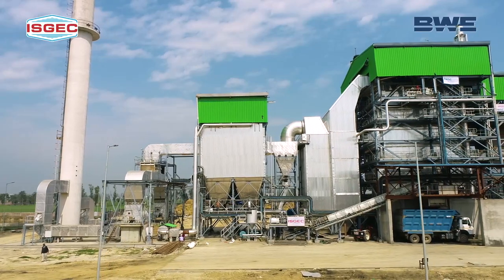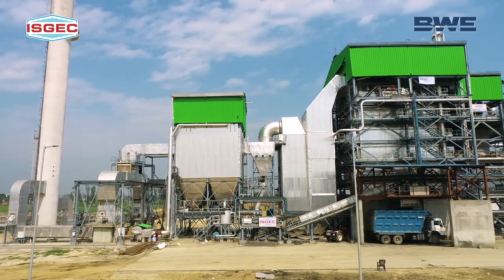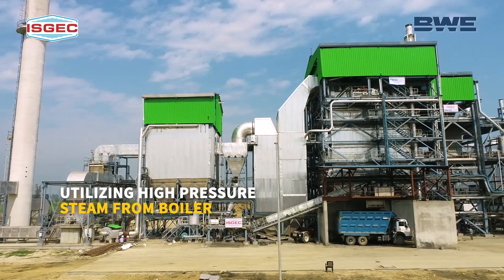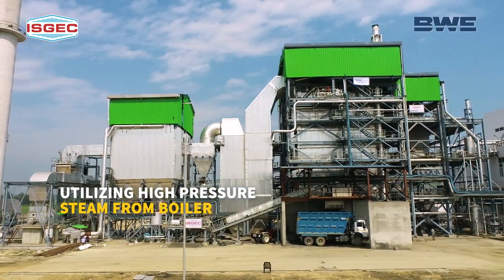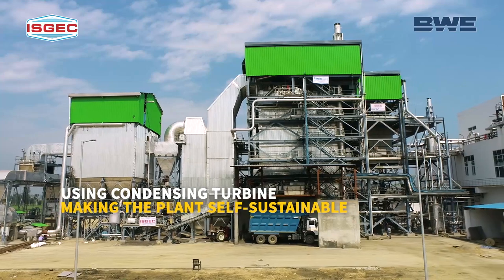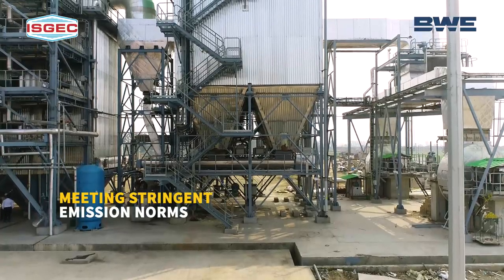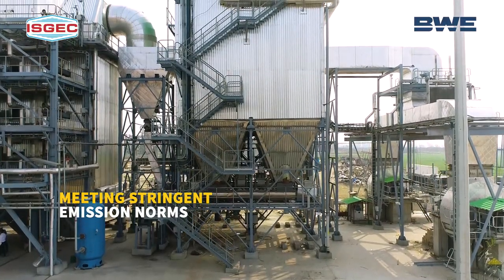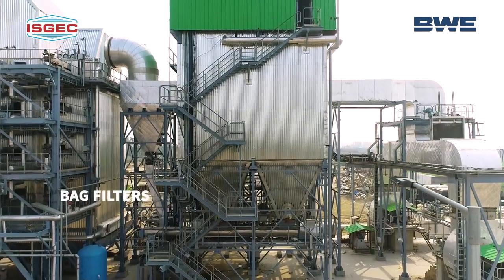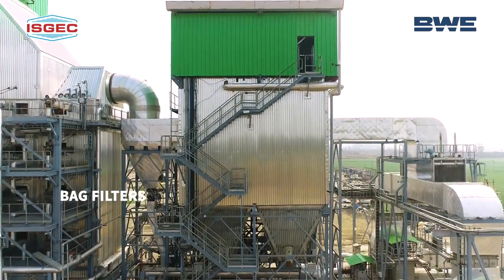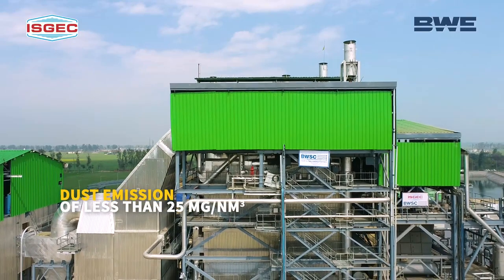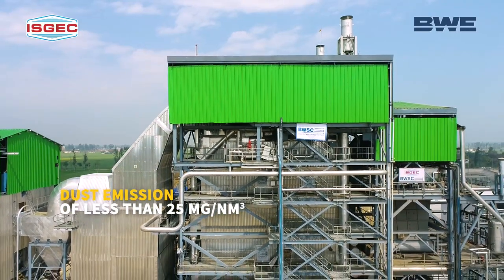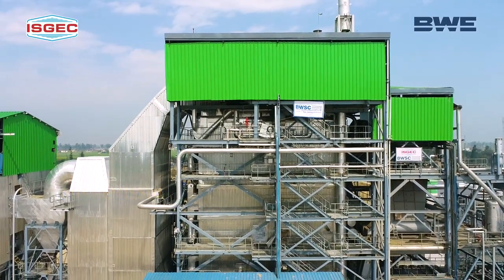Each plant is generating power through a condensing turbine by utilizing high pressure steam from the boiler, making the plant self-sustainable. To meet the stringent emission norms, the boilers are installed with bag filters, which help in maintaining dust emission level of less than 25 milligrams per normal cubic meter.